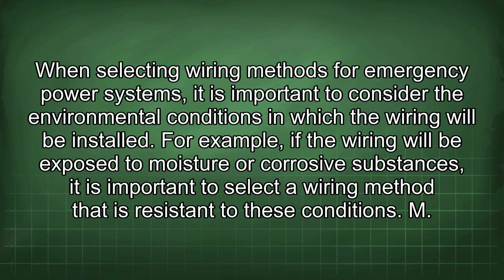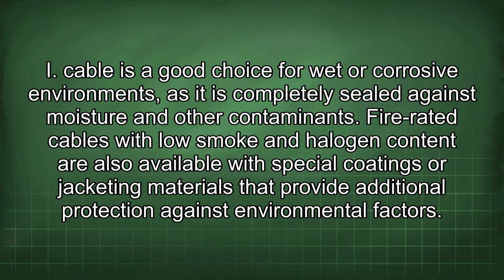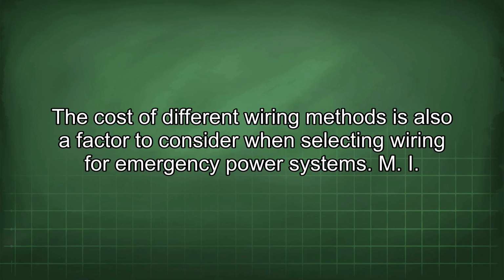When selecting wiring methods for emergency power systems, it is important to consider the environmental conditions in which the wiring will be installed. For example, if the wiring will be exposed to moisture or corrosive substances, it is important to select a wiring method that is resistant to these conditions. MI cable is a good choice for wet or corrosive environments, as it is completely sealed against moisture and other contaminants. Fire-rated cables with low smoke and halogen content are also available with special coatings or jacketing materials that provide additional protection against environmental factors. The cost of different wiring methods is also a factor to consider when selecting wiring for emergency power systems.